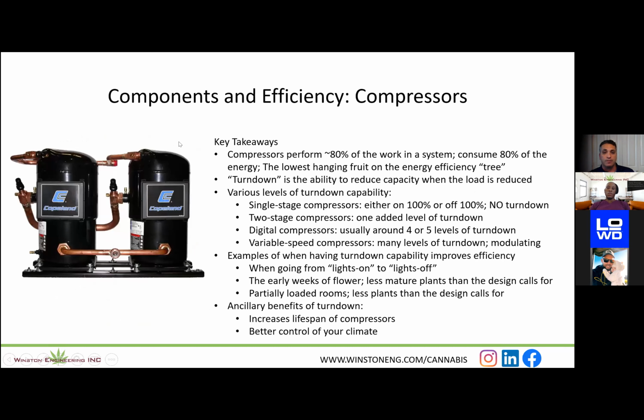So the next component, probably the most important in terms of efficiency, is going to be your compressors. The compressors perform 80% of the work in the DX and in the chilled water system. The compressor is what pushes the refrigerant. The refrigerant is ultimately what transfers the heat. So if you're looking to reduce energy usage and improve your efficiency, your compressor is going to be the lowest hanging fruit on what I call the energy efficiency tree.